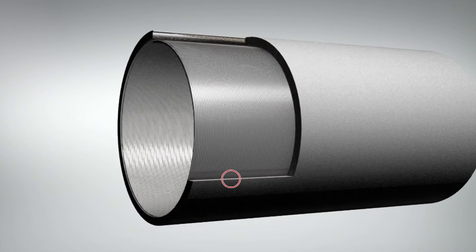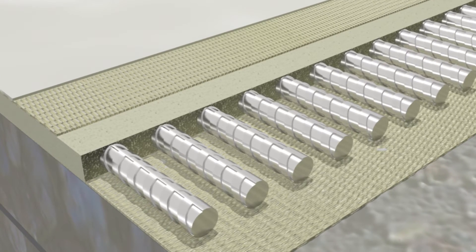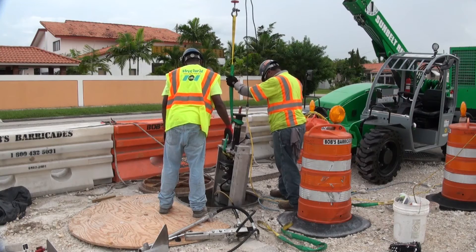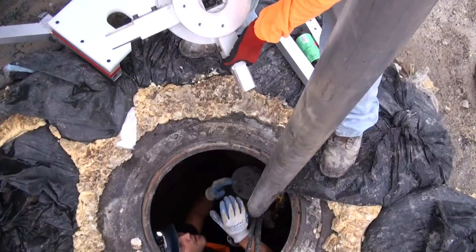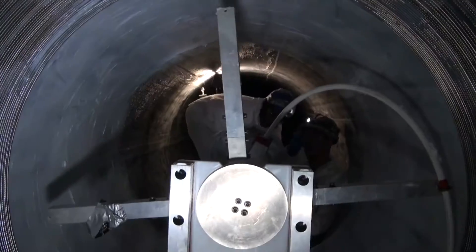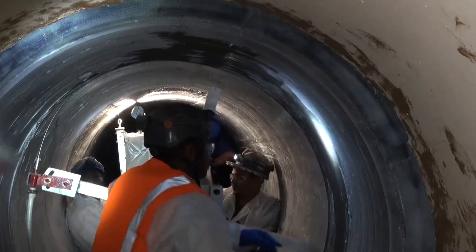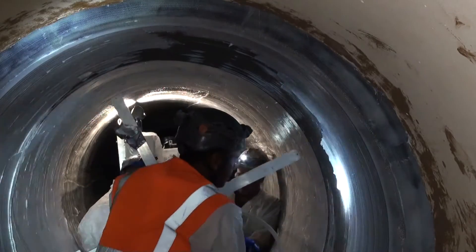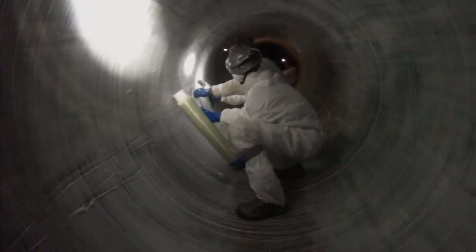The Strong Pipe system consists of high-strength steel wire installed in combination with FRP layers, custom designed to meet pressure and loading requirements. Because the Strong Pipe system is 100% trenchless, the installation took place utilizing only manhole access to complete the three 54-inch segments. Structural completed surface prep and the initial layer of FRP, giving way to the high-strength steel wire placement utilizing the automated system developed by Structural Technologies. Following wire installation, the steel was encapsulated in epoxy polymer and the final layer of FRP and top coat was installed per the approved design.